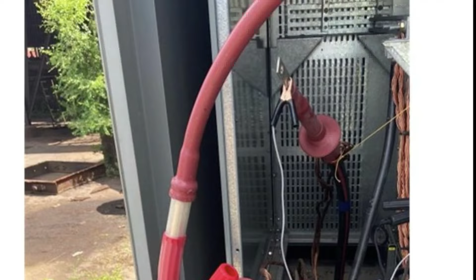Hey, Chasen, I'm sitting here watching you, and again, thanks for joining us today. But behind you, it looks like a piece of cable. What is that behind you there? This was one of the cables we took off a job just not too long ago. So 69 kV aluminum, 1500 kcmil cable, quite a behemoth. But yeah, we had that as part of our testing routine to verify that cable operated as expected.